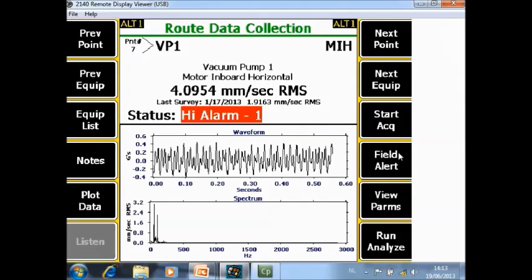Next function is F10 field alert. Let me explain the concept. You have a route with for example 50 machines. Inside every machine you have an average of 10 measurement points. That means you have a total route of 500 points. When you collect data in the field, out of those 500 points, maybe on 3 points you measure something urgent, a big problem on a certain machine.